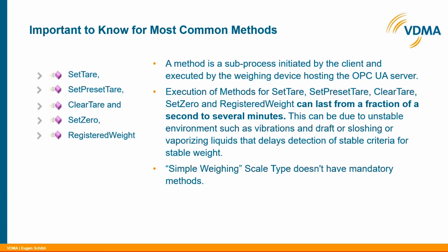A tare weight can only be captured when the weight value is stable. In an unstable environment, it can take from 1 second, 2 seconds, up to maybe 20 seconds in an extreme case, until the scale can capture a stable weight, execute the method, and provide the result.